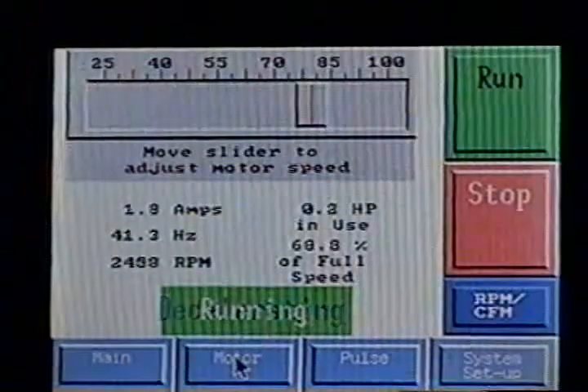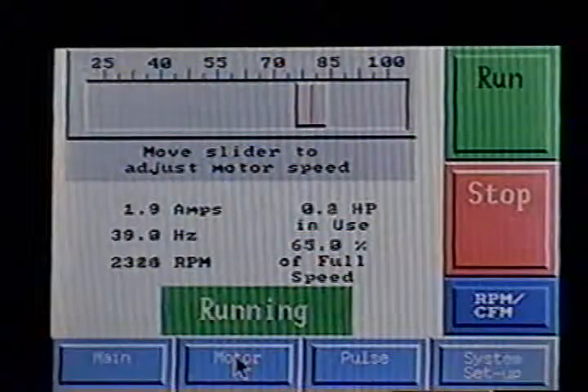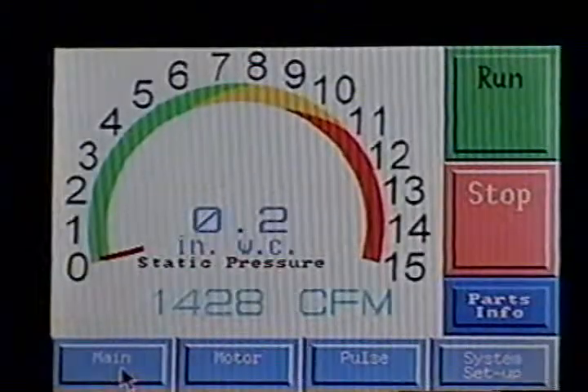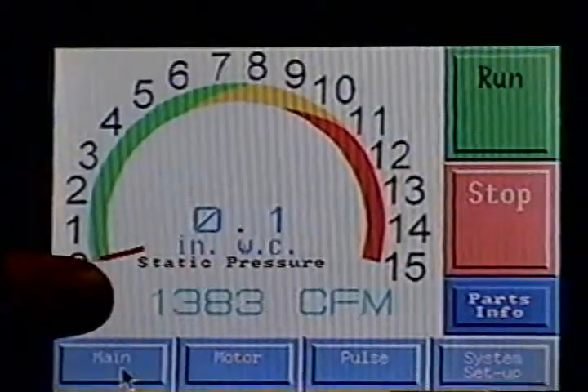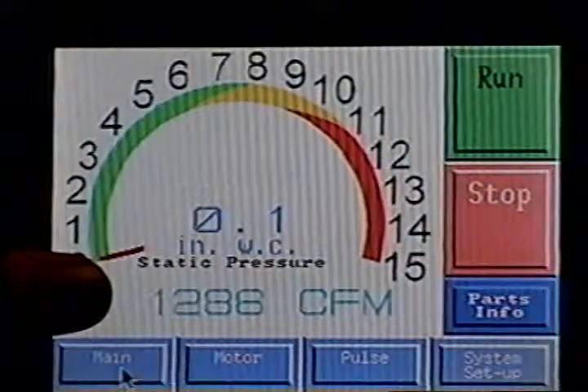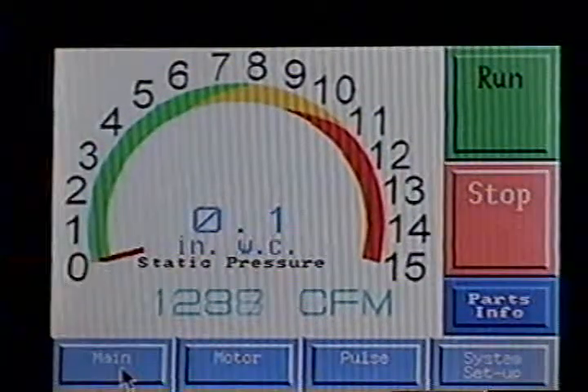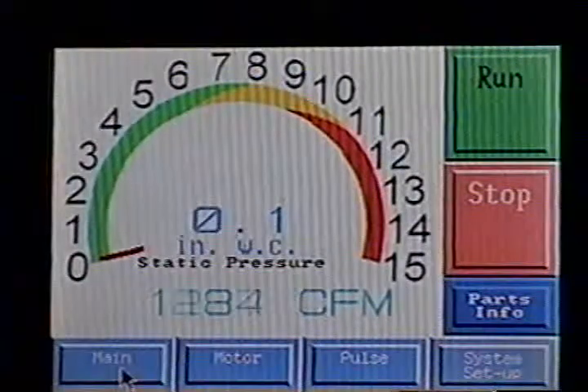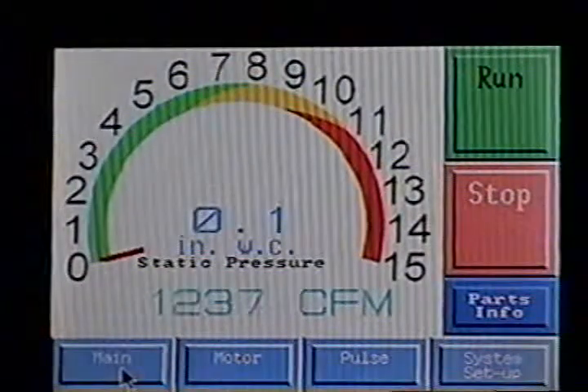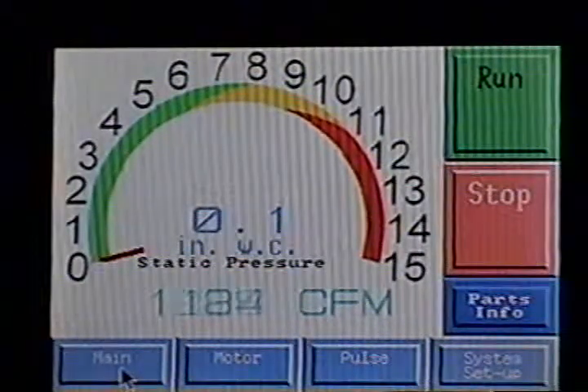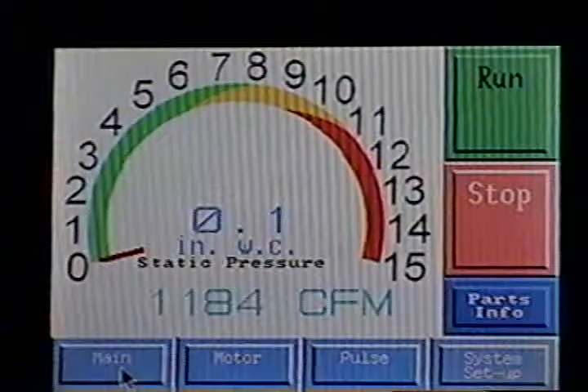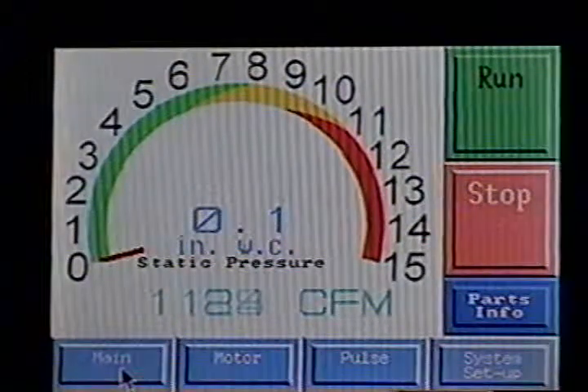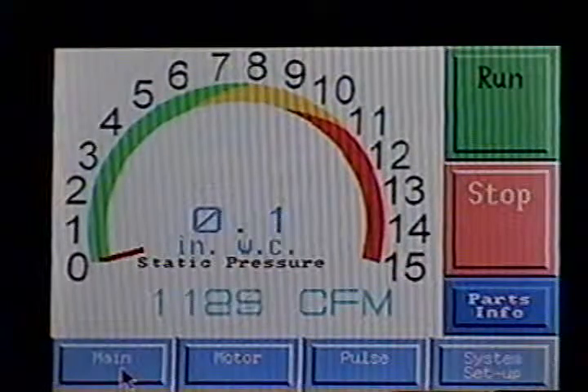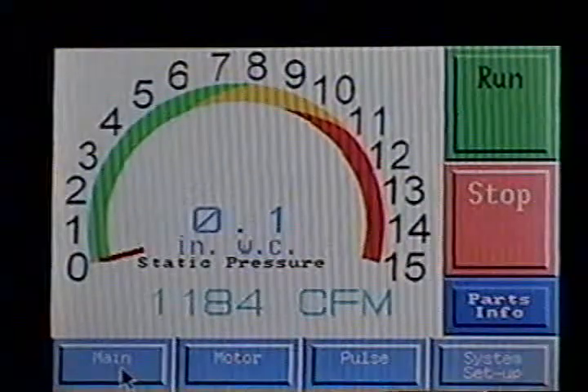And you'll hear the motor go down. It's running down at 40 hertz. And you can see here it's trying to stabilize. What do we say, 1500 CFM? Is that what I put in? It actually, because of the way the control works, it's going to dip down until it reaches a point and then it's going to come back up. It's just in the way that it stabilizes itself and the time delays in reading things. But it'll work its way back up here in just a second.